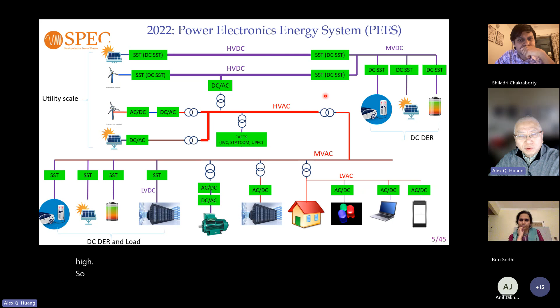So what exactly is a solid state transformer? My definition: it has to be a medium voltage power converter with isolation—typically you need galvanic isolation. Depending on whether the input is AC or the output is also AC, we can define this as type A. If you have AC, then an intermediate DC, you can define types A, B, C, D. Most people work on the so-called type D, which has multiple stages of power conversion. This is a simple classification and definition of the solid state transformer.